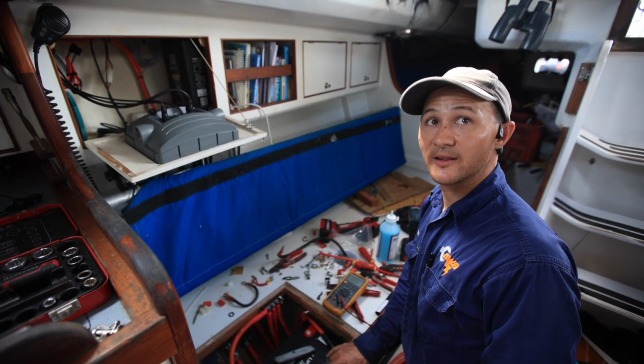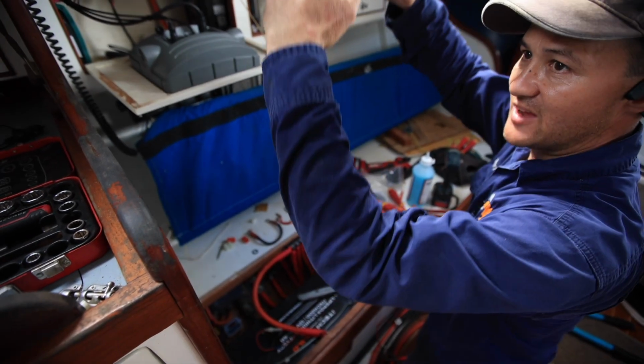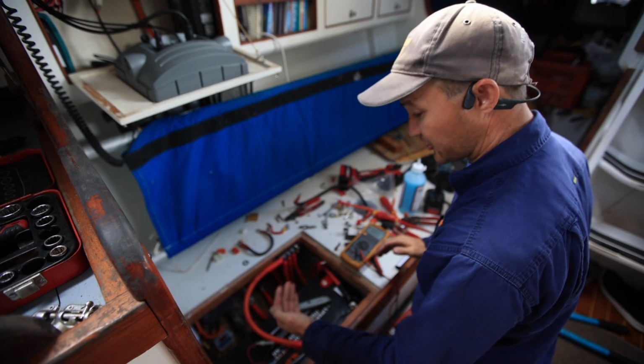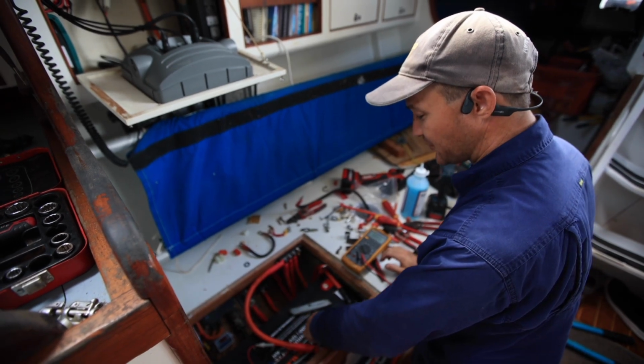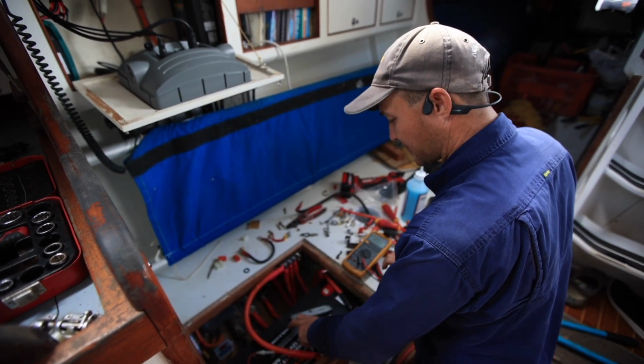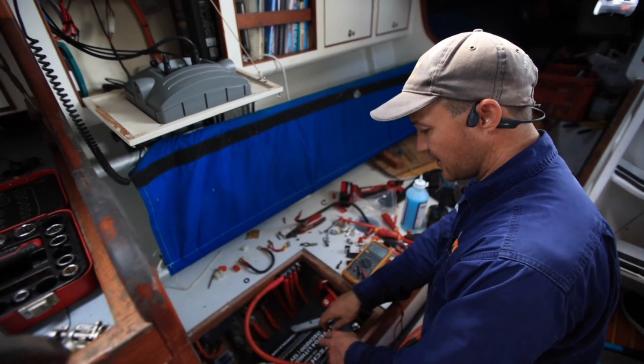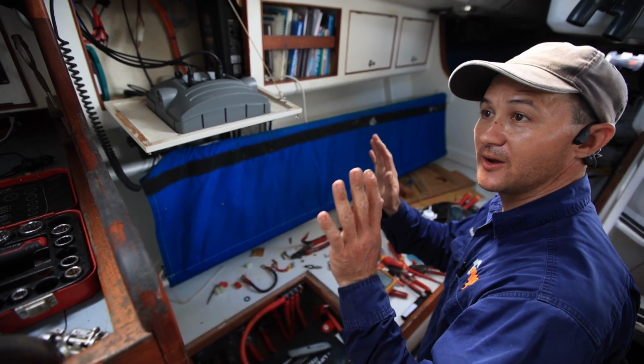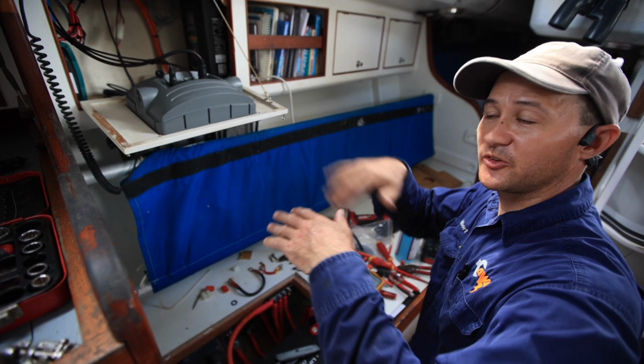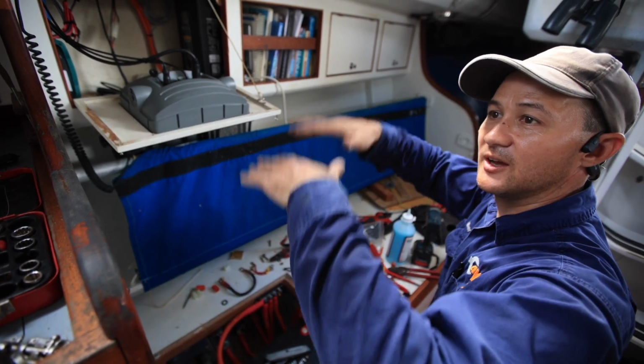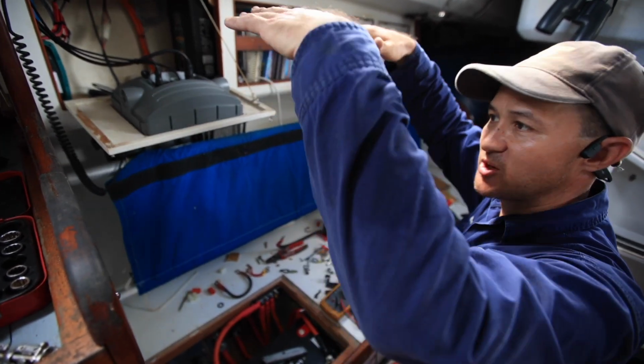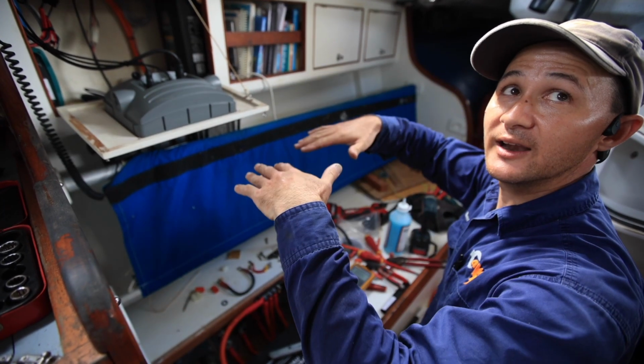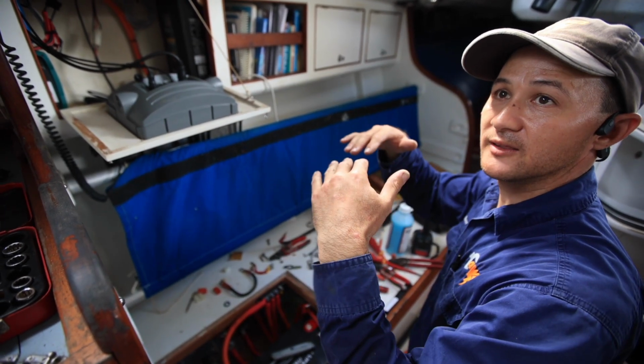Yes, that's exactly right. It also means you'll pull the batteries down evenly. What also happens with these is if you pull an overload and this battery's getting hammered down unevenly compared to that one, this BMS will go no, it'll turn off, and then the other battery will turn on. So the BMSs will basically be doing their own things instead of pulling down together like that, which is what you want with all lithium batteries.